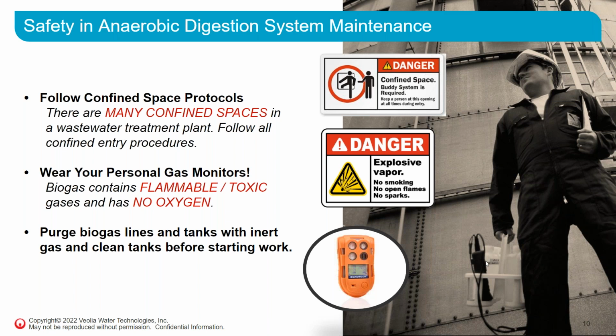because we know that biogas contains flammable and toxic gases, and especially in an anaerobic environment, it means that there is no oxygen. So please always purge the biogas lines and tanks with an inert gas like carbon dioxide or nitrogen, and clean the tanks before starting work in those confined spaces.